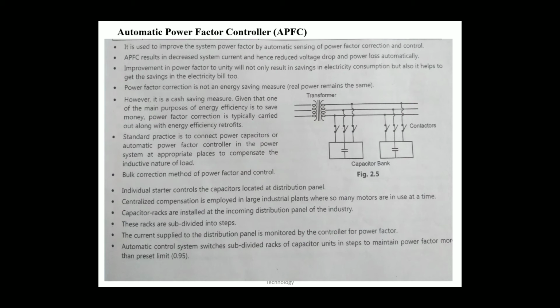However, it is a cash saving measure, given that one of the main purposes of energy efficiency is to save money. Power factor correction is typically carried out along with energy efficiency retrofits. Standard practice is to connect power capacitors or an automatic power factor controller in the power system at appropriate places to compensate the inductive nature of the load.